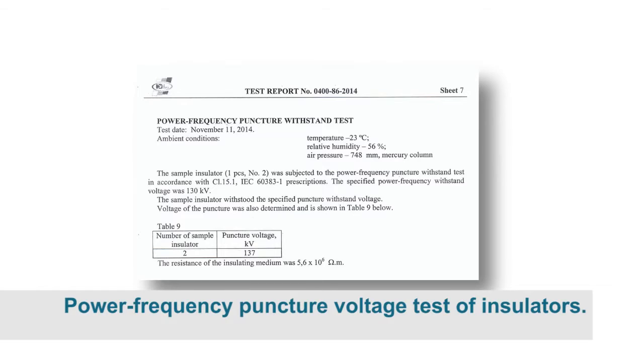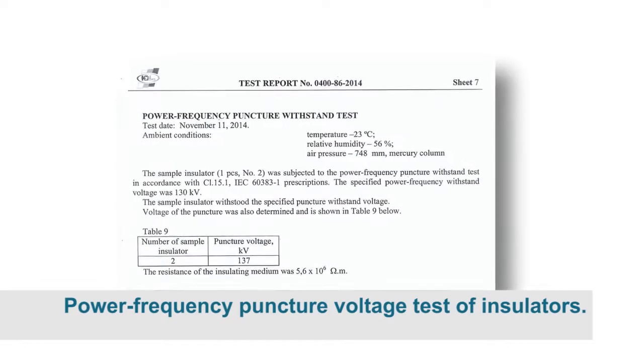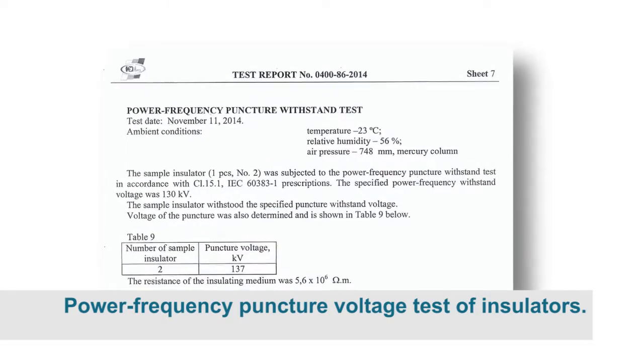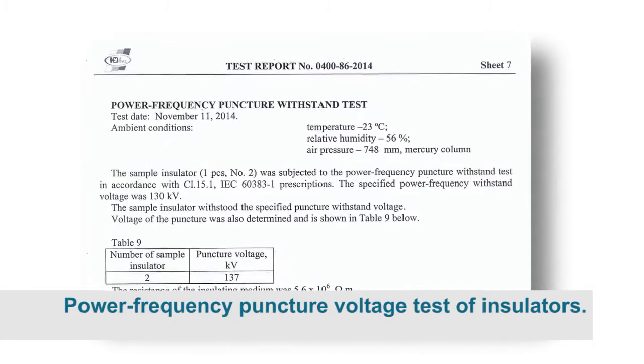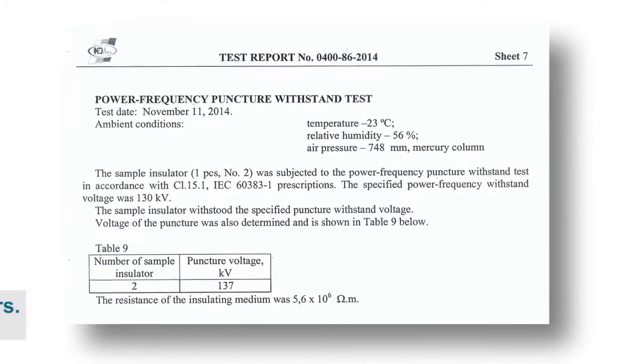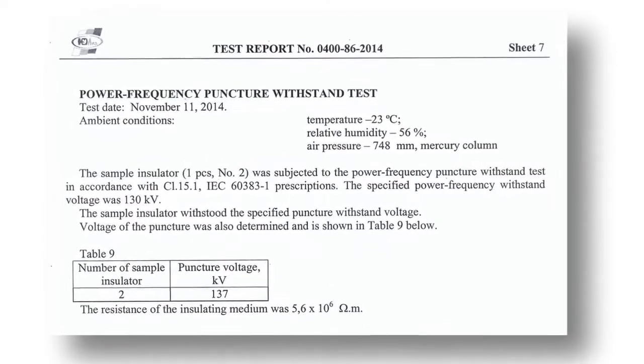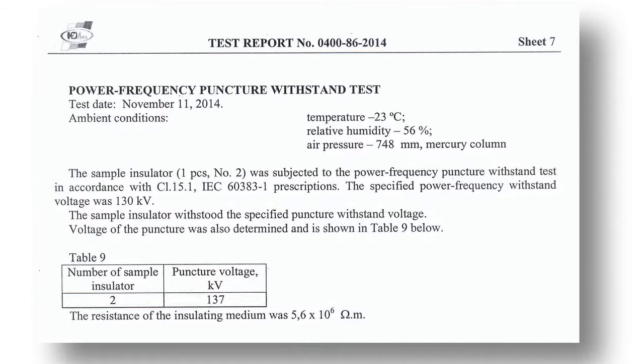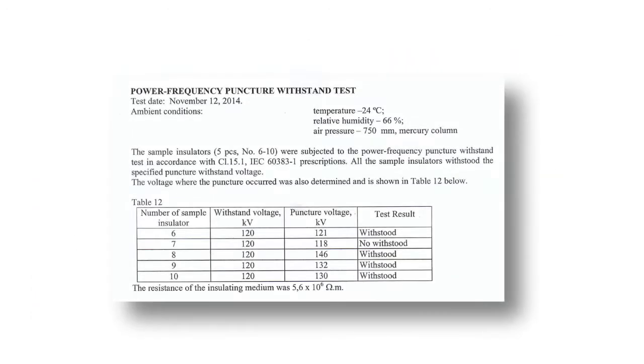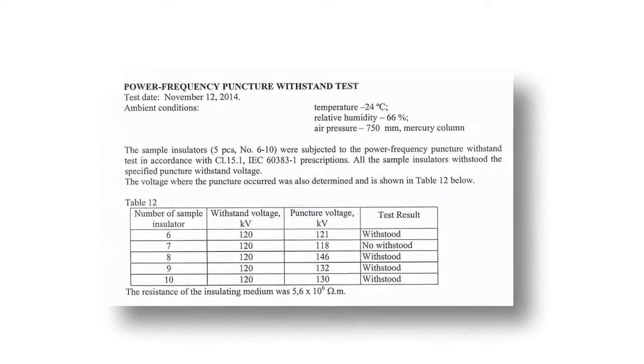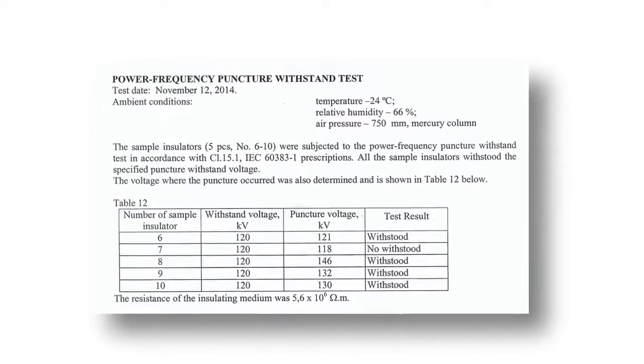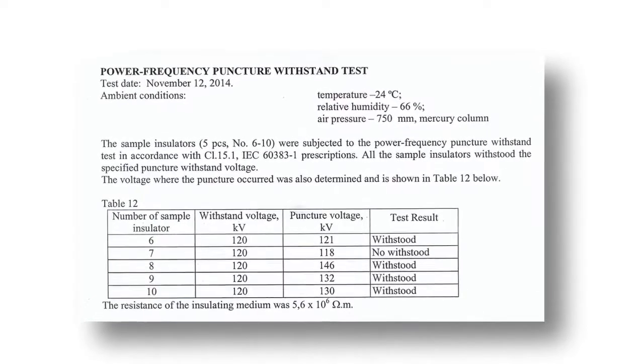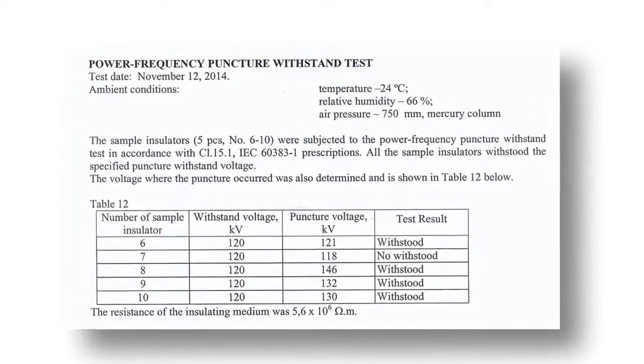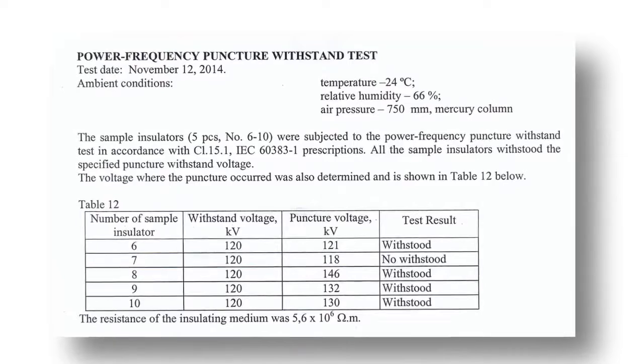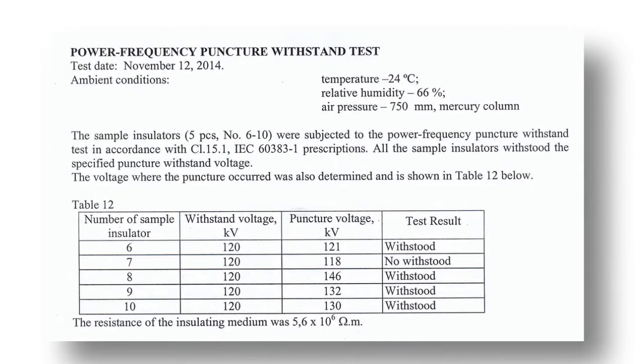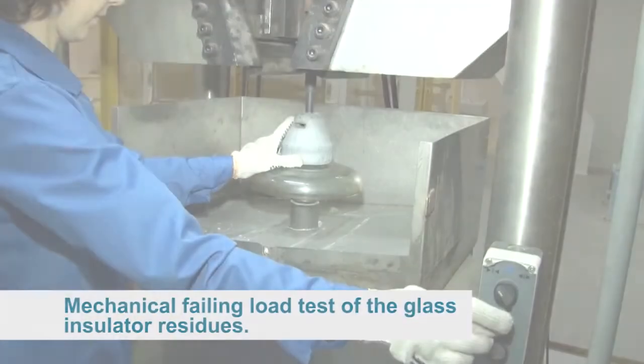Power frequency puncture voltage test of insulators of type PS70E. The tested insulator passed the test because the puncture had occurred at a higher voltage than the standard voltage. The insulator of type PS70E meets the IEC requirements. Power frequency puncture voltage test of the insulators of type PS12A. The insulator did not pass the test because the puncture had occurred at a lower voltage than the standard voltage. The insulator of type PS12A does not meet the IEC requirements.